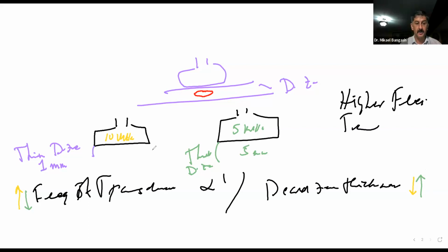Now please don't come back to me a couple of months from now and say, Mike, we used a 10 megahertz transducer, and the dead zone for that is 2.8 millimeters, it's not 1 millimeter as you told us back in the days. Well, this is just to give you a sense of the relationship.